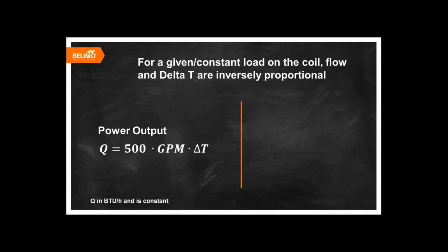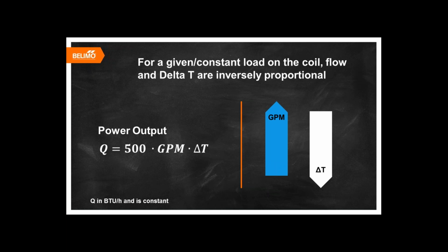Using the formula on a coil, flow and delta T are inversely proportional, which means as our flow, which we measure here in gallons per minute, increases, the delta T at our coil will decrease.